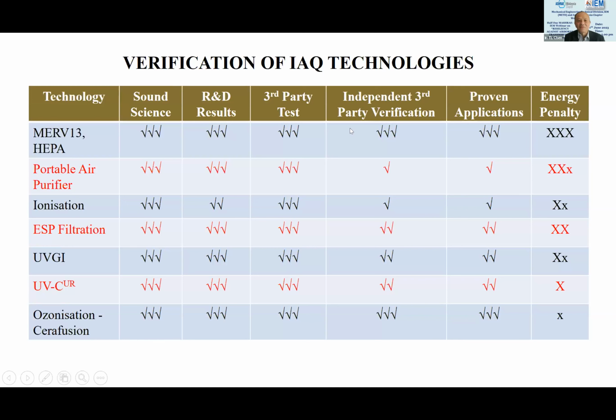Third-party test maximum, independent verification always there, proven applications plenty around, no doubt about it. But high energy penalty, because the increase in static pressure means fan power has to increase, so we pay the penalty. Even so, that penalty is still less than if you bring in more outside air, which increases the aircon load. So it's still a balance.